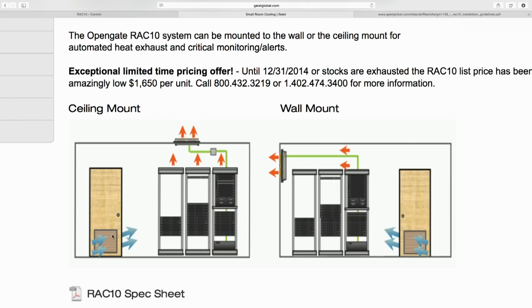The problem is if people put a vent in the door but there's no way for the air to circulate, everything will still overheat. So you put a vent in the door, a normal vent, and connect a fan like this to the ceiling or side of the room. When the fan turns on, it pulls air through the room and cools the entire space. So you don't need a dedicated HVAC system because this pulls the ambient air out of office spaces that are most likely kept at a reasonably cool temperature.